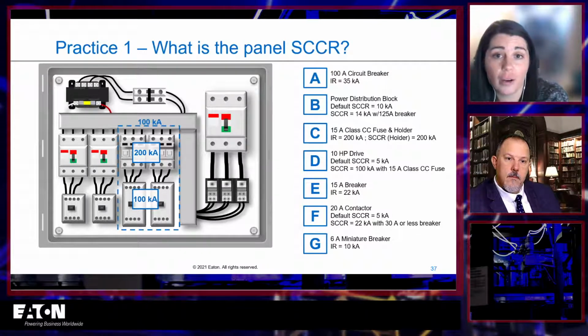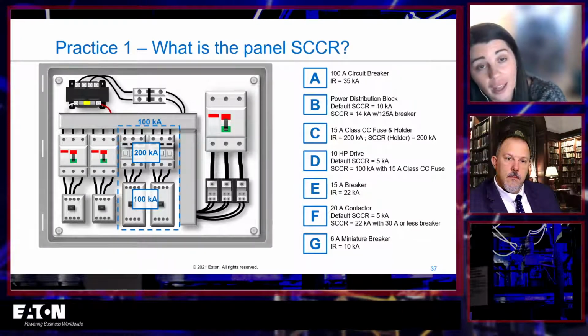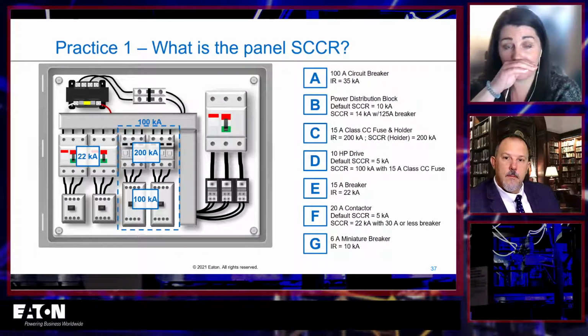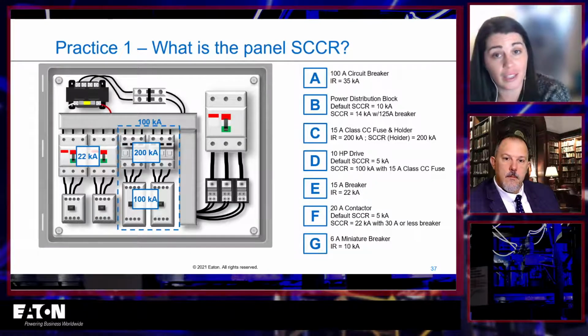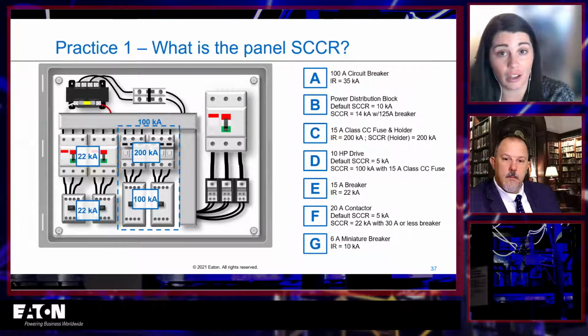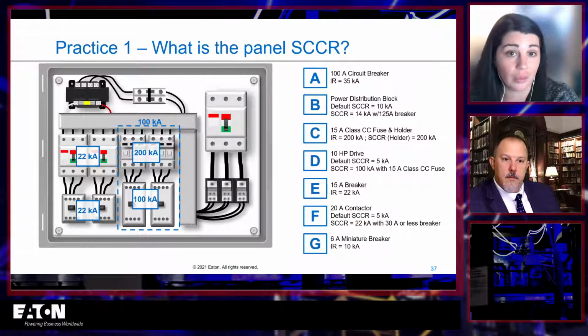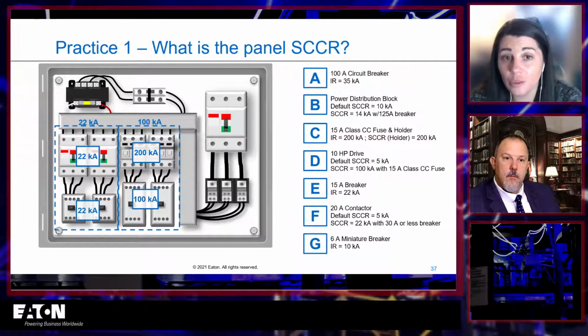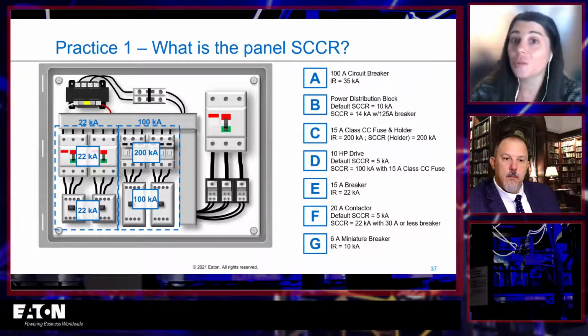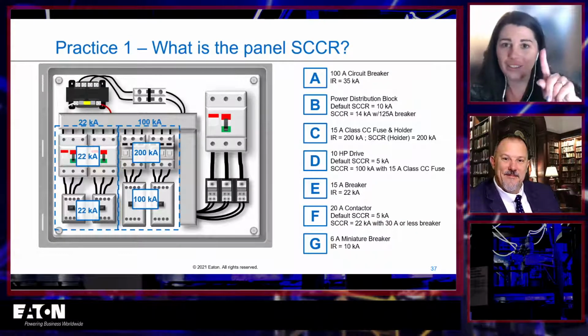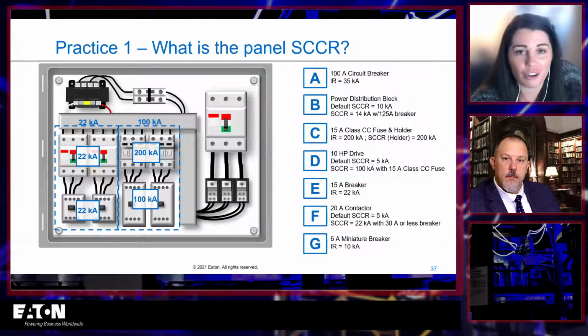I have a 15 amp breaker with an interrupting rating of 22 kA. So we can just go ahead and apply that. And then F is a 20 amp contactor. It would have a default rating of 5 kA, or an SCCR of 22 kA with a 30 amp or less breaker. I'm using a 15 amp breaker that is 30 amps or less, so I have a 22 kA short circuit current rating there. My short circuit current rating for my whole branch is the lowest value between 22 and 22, so it's going to be 22. And that's step one of determining my panel short circuit current rating.